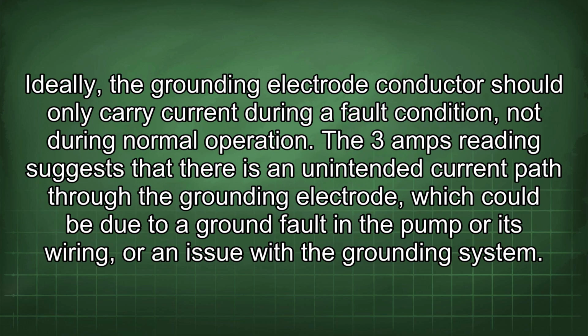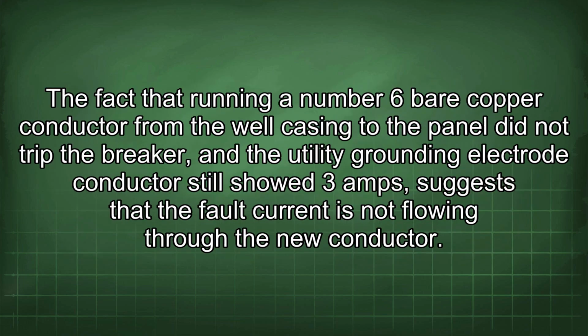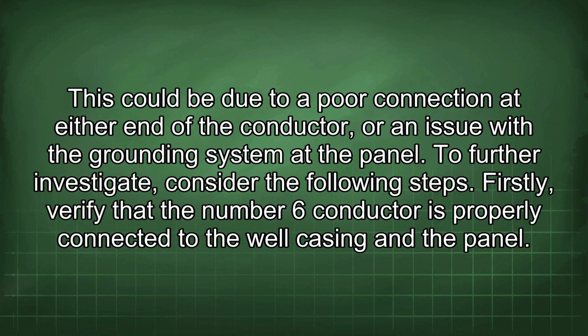Ideally, the grounding electrode conductor should only carry current during a fault condition, not during normal operation. The 3 amps reading suggests that there is an unintended current path through the grounding electrode, which could be due to a ground fault in the pump or its wiring, or an issue with the grounding system. The fact that running a number 6 bare copper conductor from the well casing to the panel did not trip the breaker, and the utility grounding electrode conductor still showed 3 amps, suggests that the fault current is not flowing through the new conductor. This could be due to a poor connection at either end of the conductor or an issue with the grounding system at the panel.